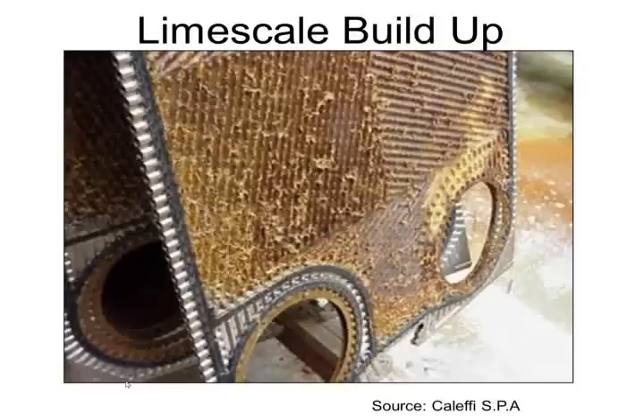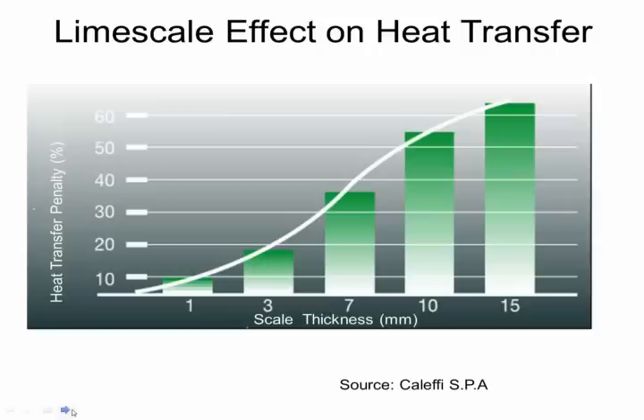In front of you is a flat plate heat exchanger that has suffered the effects of lime buildup. This is a section taken out of the heat exchanger. And the thing about limescale, first of all, it starts to plug up the passageways, so the pump starts to operate less effectively, or basically you start starving that exchanger of flow and thus heat transfer efficiency. And then the other thing is that the limescale is actually an insulator. And so as you start building up, you start losing the effectiveness of sending heat across that heat exchanger, perhaps into your snowmelt zone, or perhaps into the domestic side of your solar thermal system.